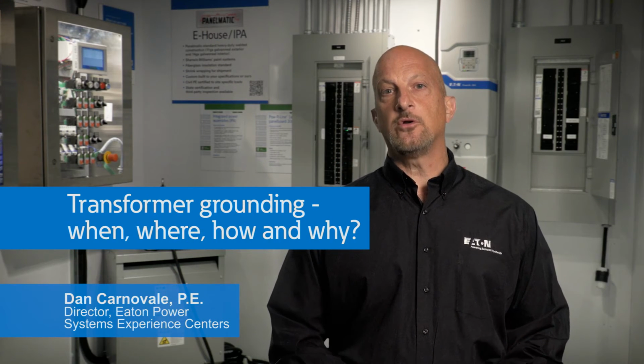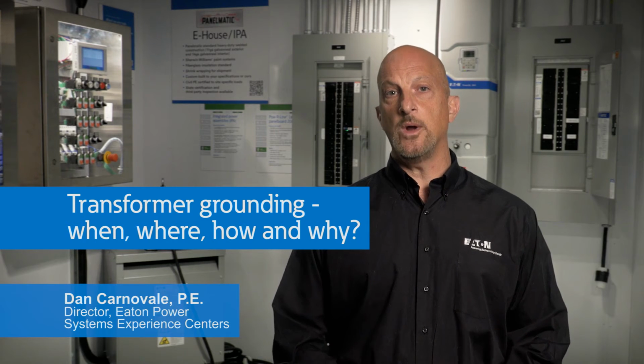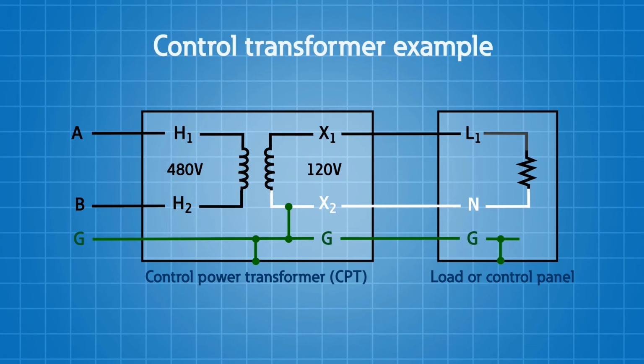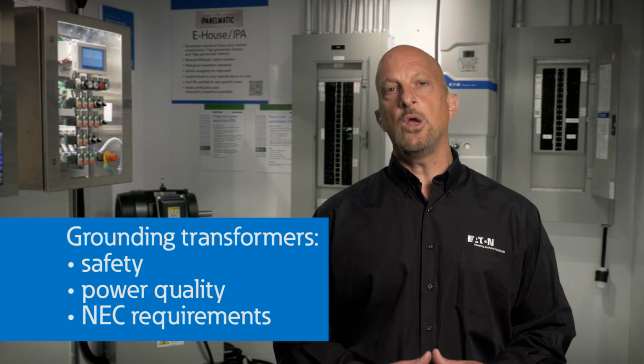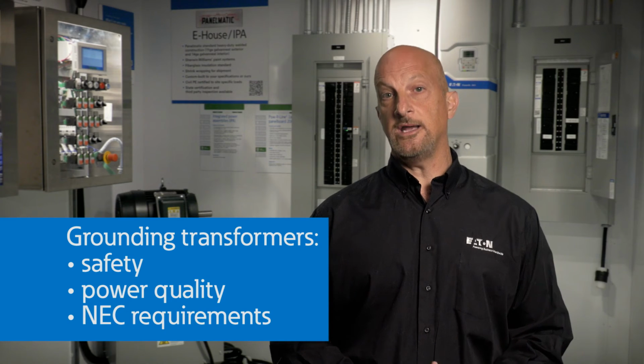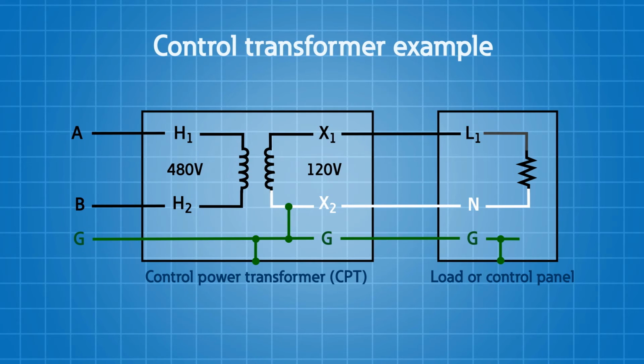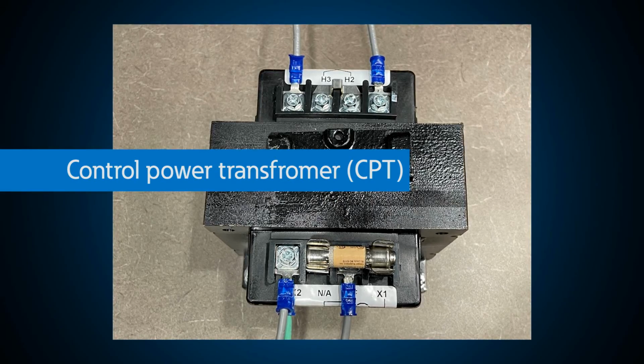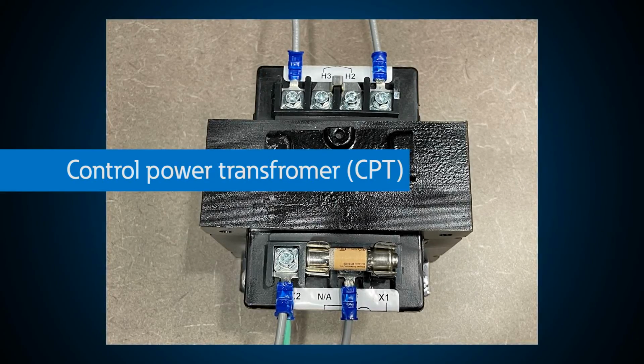With respect to grounding, transformers are often an area of concern and discussion regarding when, where, how, and why to ground the transformer. This is a simple single-phase example of a transformer like a 480 to 120 volt control power transformer. Considering the secondary windings, one of the two legs, typically X2, would be connected to ground. This would allow you to establish a known reference on the secondary of the transformer when this is required for safety, power quality, or by NEC requirements. X2 is also considered the neutral conductor for typical low voltage applications and would only be grounded at the transformer and at no other point downstream on the circuit fed from the transformer. For this situation, a simple wire connecting X2 to the incoming ground wire coming from the primary of the transformer would suffice for a control power transformer.